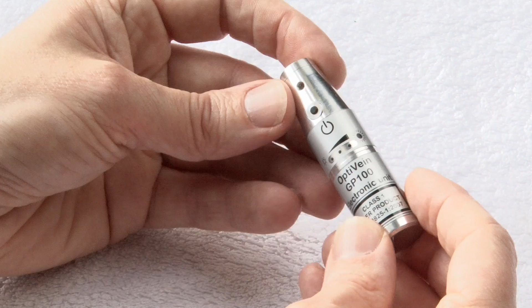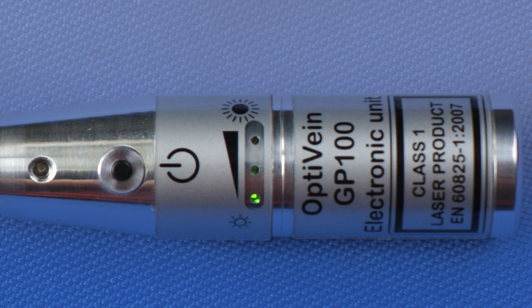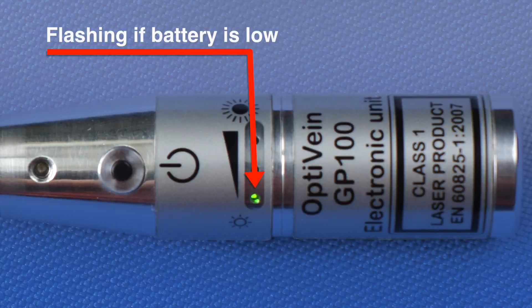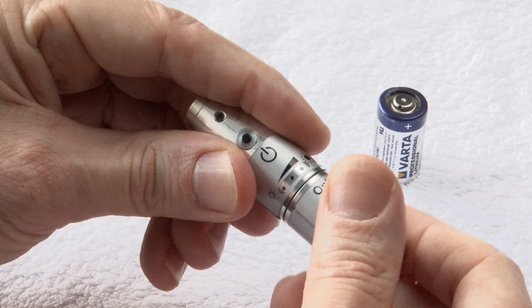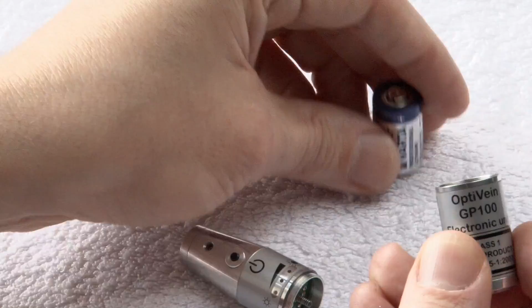The OptiVein electronic unit is powered by CR2 batteries. A battery low condition is indicated by one of the LEDs, corresponding to the power level, flashing. The battery should be changed immediately to ensure proper operation of the OptiVein electronic unit. To replace the battery, unscrew the battery compartment cover, remove the old battery, and insert a new 3-volt CR2 non-rechargeable battery.